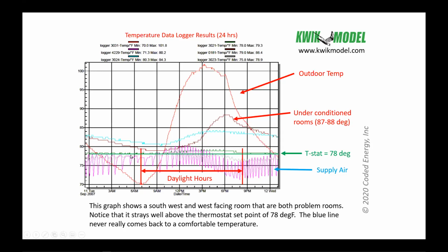Well, look at this pink line here. This pink line is the temperature of the air coming out of the supply register. We call those icicles. So when this temperature drops like this, you see this sharp downward spike, that is the air conditioner turning on. So the air conditioner turns on, the supply air temperature drops down. And when you hit that little peak at the bottom and it starts going back up, that tells you that the air conditioner turned off. So now the temperature is rising back up. So when it comes down, it's on.